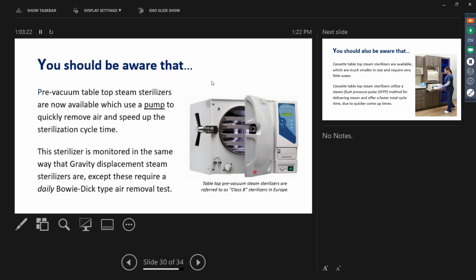They could purchase pre-vacuums, but they cost $2,000 or $3,000 more. If you're only paying $2,000 or $3,000 for a gravity sterilizer, why would you pay $6,500 for a pre-vacuum? Well, it's a faster cycle, more convenient. Somehow the vast majority of North America do not use pre-vacuum.